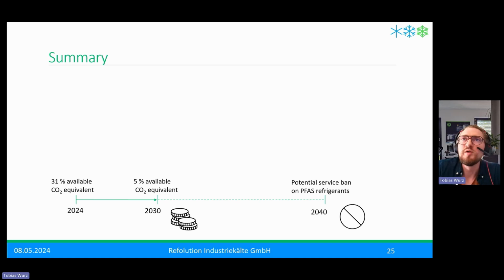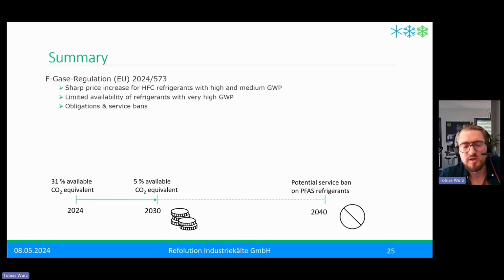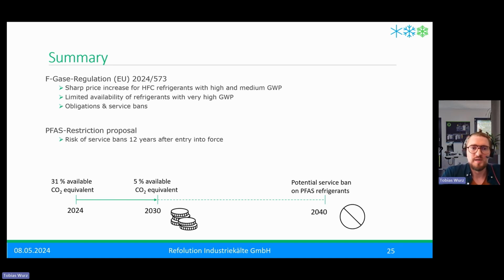Okay, so our summary. We have this F-gas regulation, which means that the HFC refrigerants will rise extremely in price until 2030, where we only have 5% available CO2 equivalent. And even for higher GWP refrigerant, it could be that you don't get this anymore. So even if service is allowed, you don't get this refrigerant anymore. And the PFAS restriction proposal means there could be a service ban 12 years after entry into force, which we expect could be around 2040. But of course, if you buy equipment with PFAS refrigerant today, maybe you have 16 years, because 2024 to 2040 is 16 years. You have to decide if this is a normal life of a refrigeration unit.